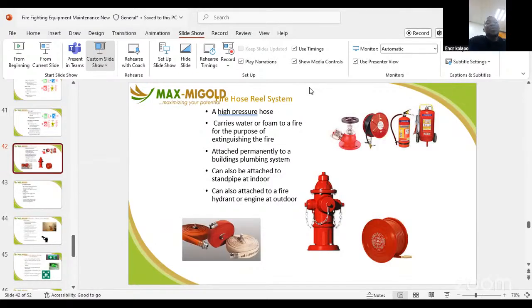And if it is prolonged for a long time, or we need to knock off power supply to that building, the diesel engine fire pump then comes into play. The aim is to push water wherever the valve has been opened or the hose reel has been operated, just to ensure water is available at least 10 bar, or between 7 to 10 bar, to extinguish the fire. Next slide.